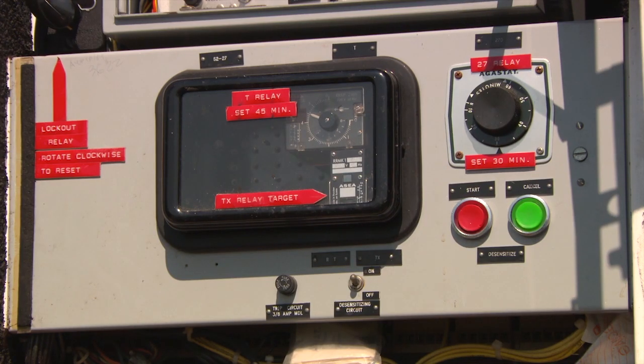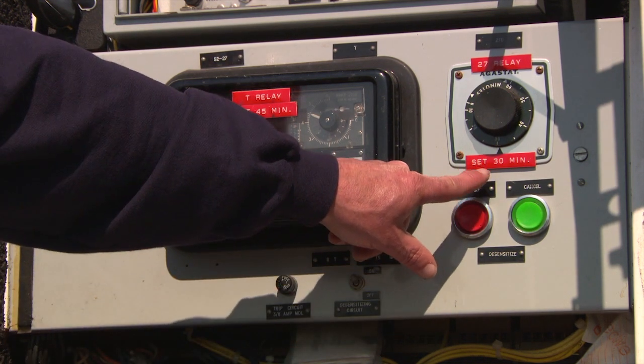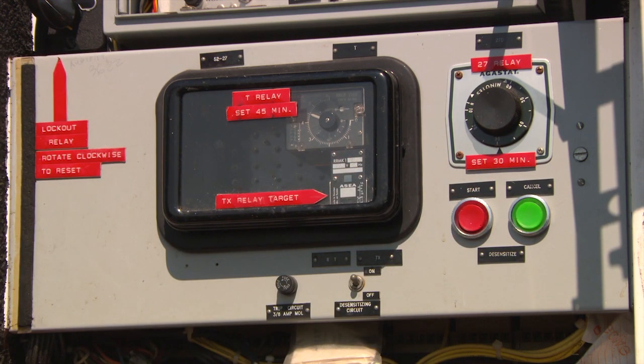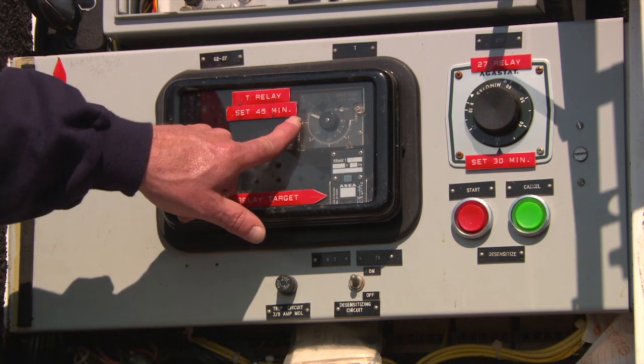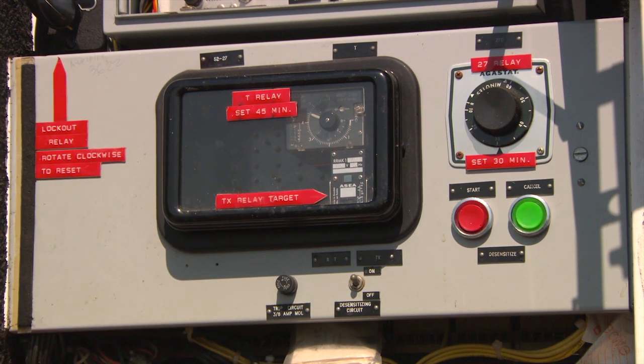Verify the settings on the desensitizing relays located in the recloser control cabinet. The 27D relay setting should be placed at 30 minutes. The T relay setting should be placed at 45 minutes. These settings provide cold load pickup ability, allowing the reclosers to carry double the resistor settings for a set period of time.